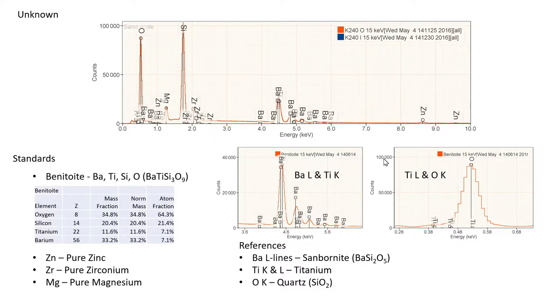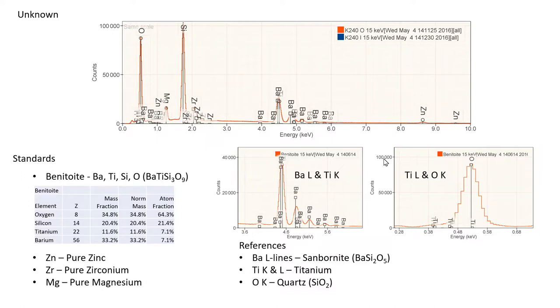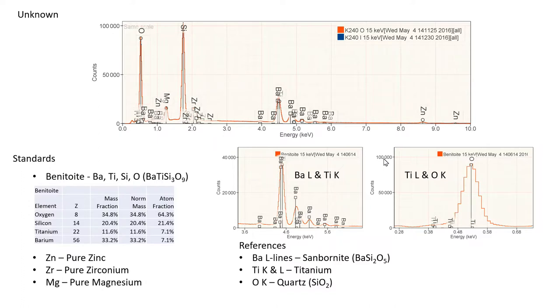The primary standard is going to be Benitoite, which has two serious overlaps associated with it. First, barium and titanium have an overlap in the barium L and titanium K regions. And then titanium also has an overlap with the oxygen K. At first blush this might seem to be a poor choice of standard, but the standard happens to match quite well with the unknown, so it is probably a good choice in terms of getting an accurate quantification.